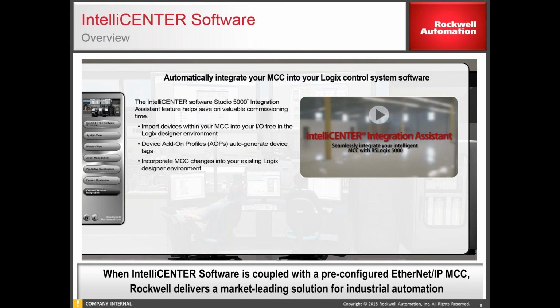Okay? So if you want to take some actions on some of that data, you don't have to go in and set up all those tags. You can just import the information right into your ControlLogix. So it'll save you a lot of time when it comes to commissioning, troubleshooting, and then it will minimize mistakes as well, right? So if you don't have to go in and manually type in all those tags, if it's going to be automatically done for you, you're going to minimize fat fingering something, right?